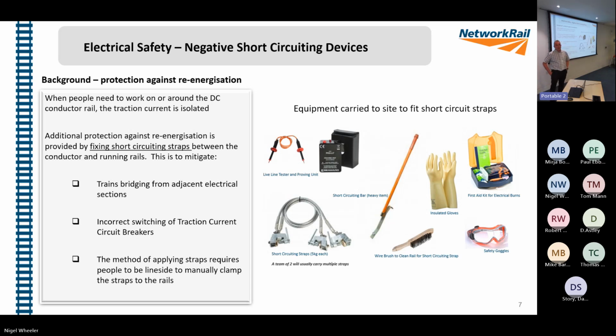We used to turn off the conductor rail and then fit short circuit straps, which is the equivalent of earthing on an OLE system. We need to do that because otherwise trains can run in from live sections, and through the bus-line connections on the train, they can liven up the conductor rail. Someone could make a mistake in the control room. So effectively, that short circuit strap gives the integrity of that isolation. It means you cannot have dangerous voltage on that conductor rail, which means when the person issues the permit to work, everyone knows within that set area it is safe.